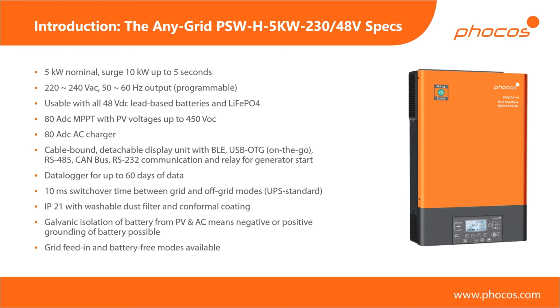We have an 80 amp MPPT, which is integrated in the unit with up to 450 volts tolerance of voltage from your PV side. So we have a very high maximum PV voltage for this type of inverter. We also have an 80 amp AC charger. So of course this 80 amp is battery side. So you can use the grid or any other AC energy source to charge your battery.